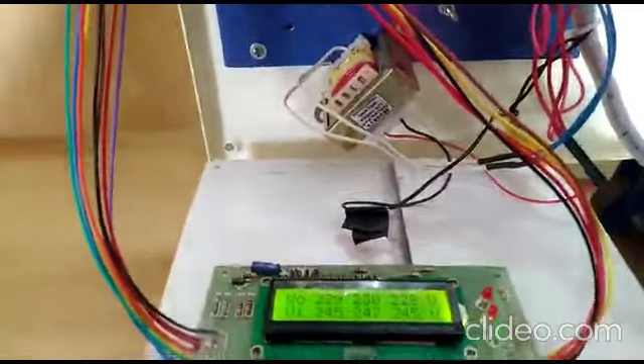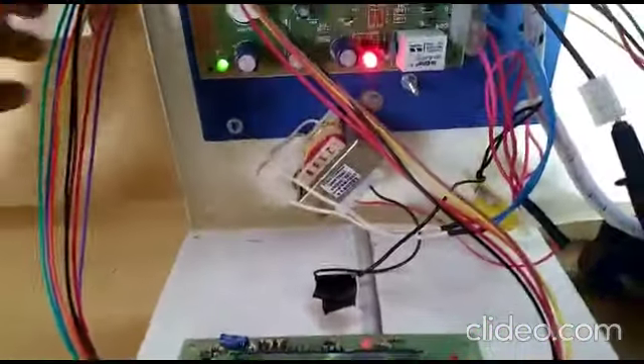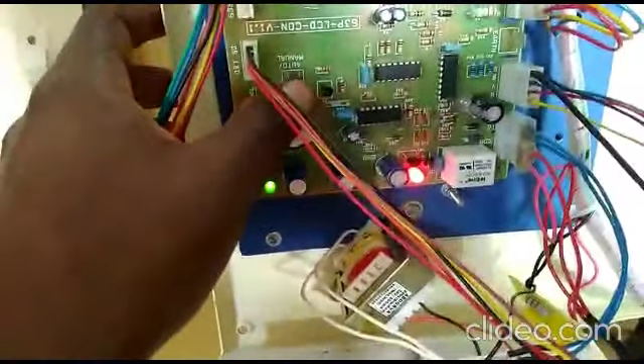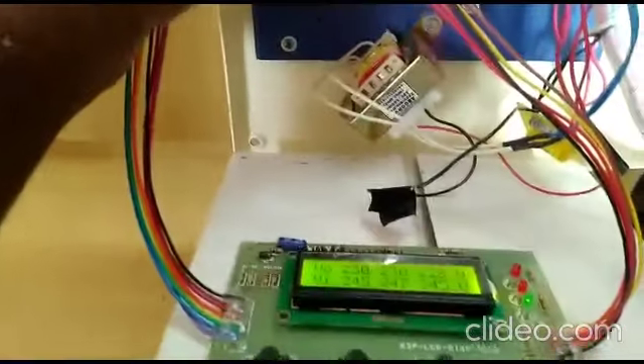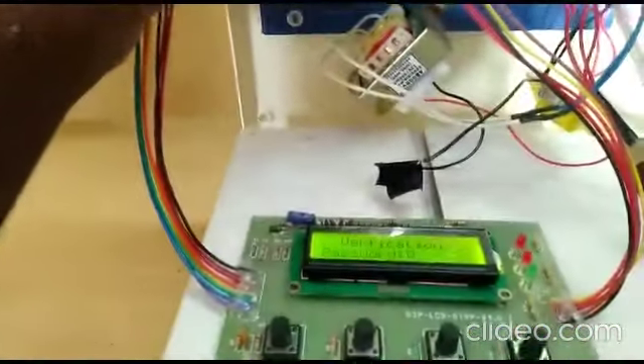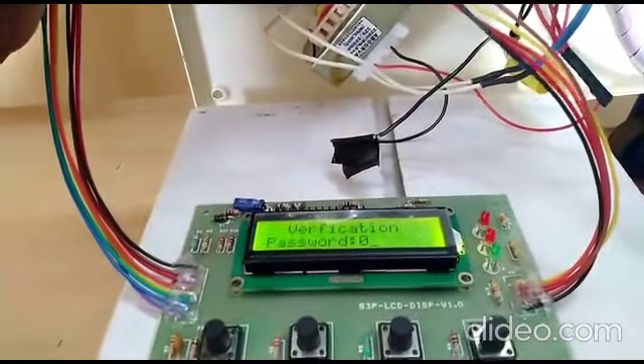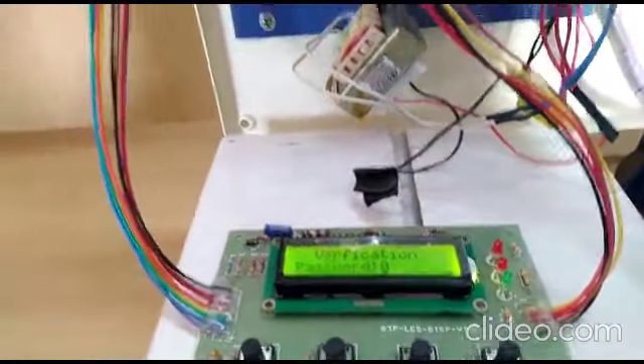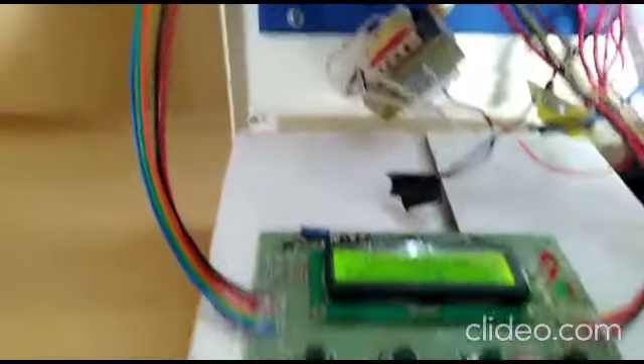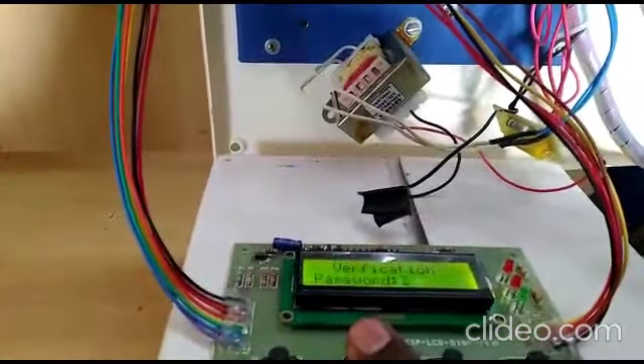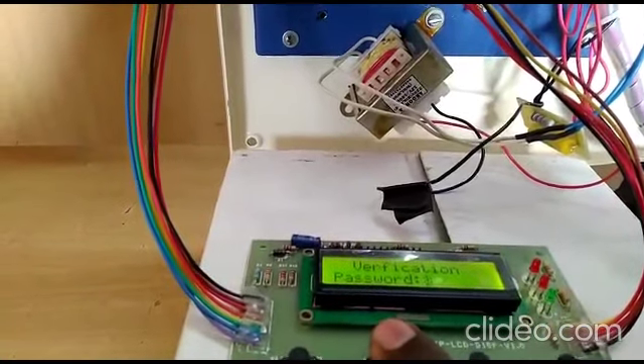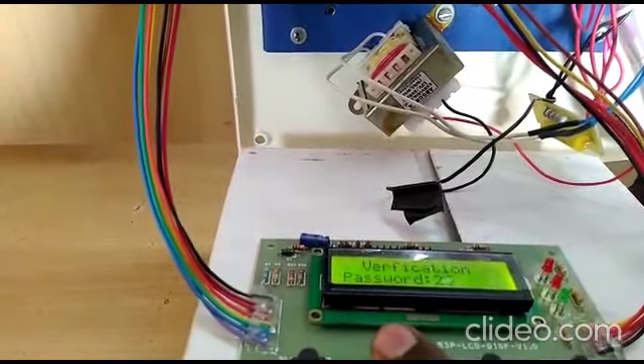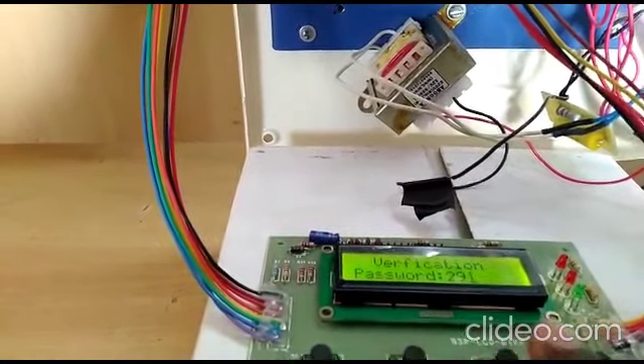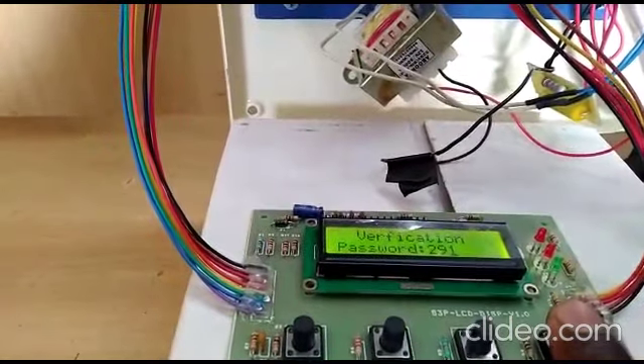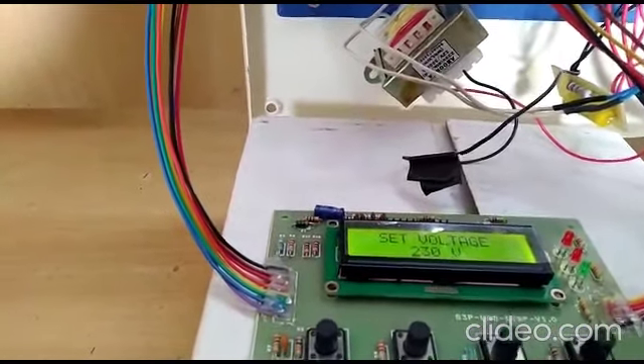How to enter the set mode? We need to press the auto manual button with a long press. When it enters the verification password setting, we can release the button. Now we should set the password. The password is 291. Then press the next button, log. Now setting the parameters.